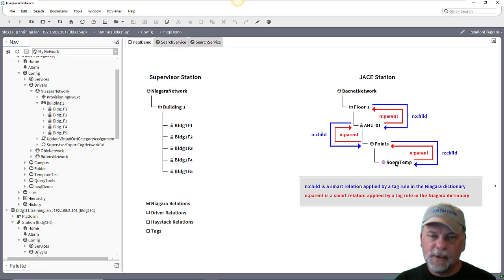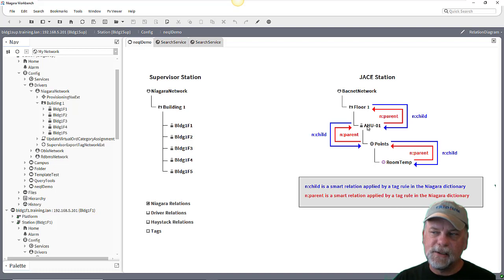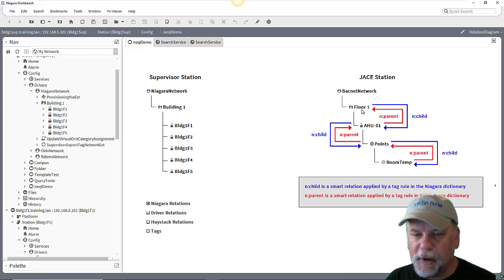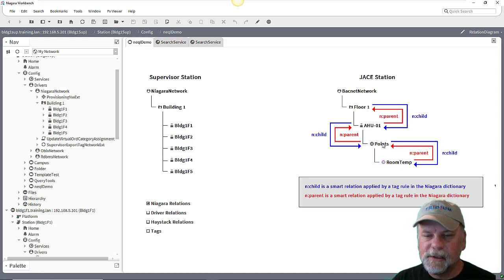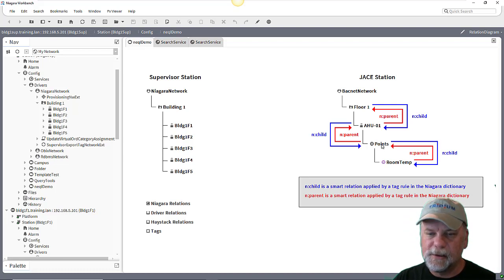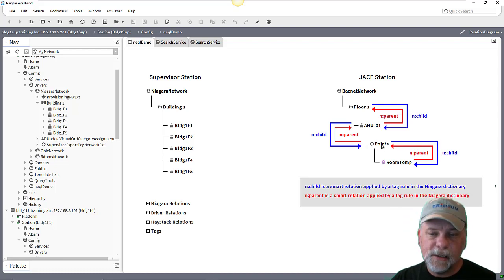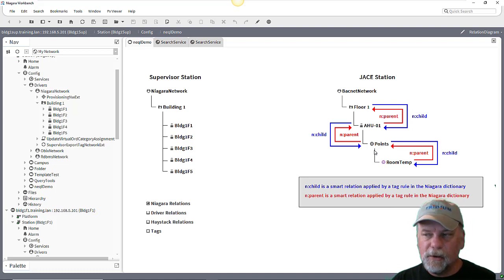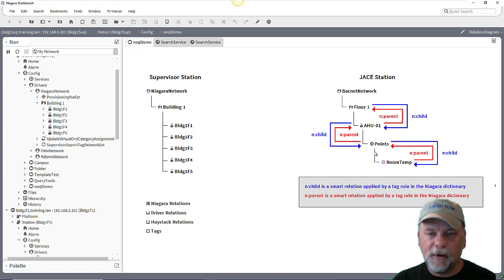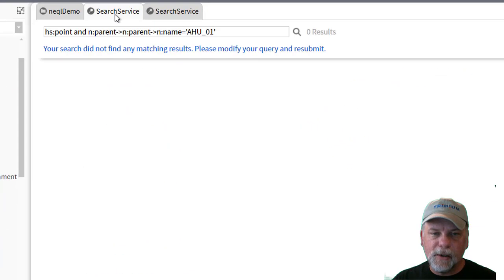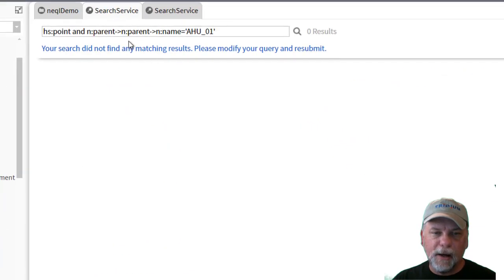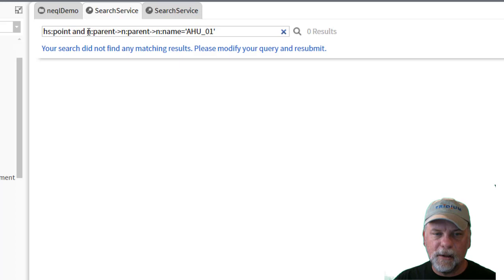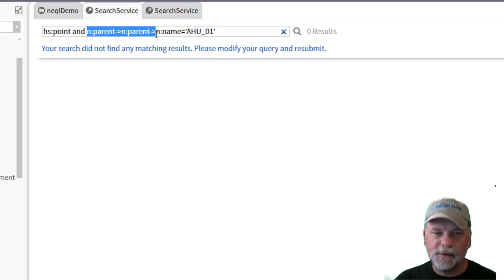Now I don't expect this to find anything, and the reason for this is that the system database indexes the control points and it indexes the devices and the device folders and the networks, but by default it doesn't actually index the point device extensions. You can change it. You can update the system database queries to include the point device extensions, but by default they're not included.